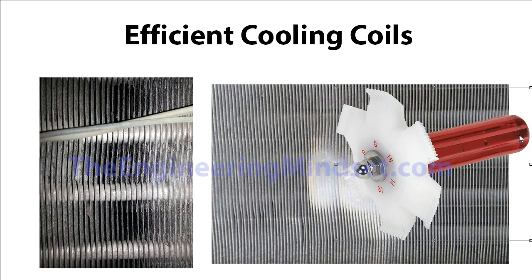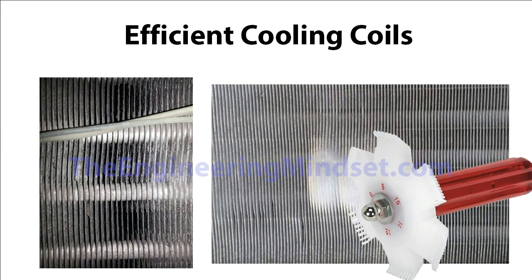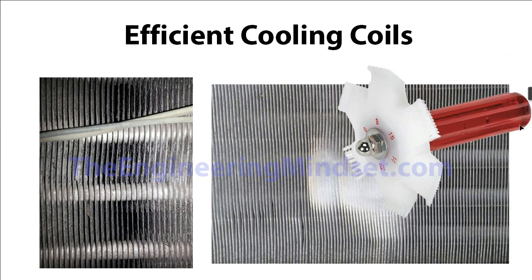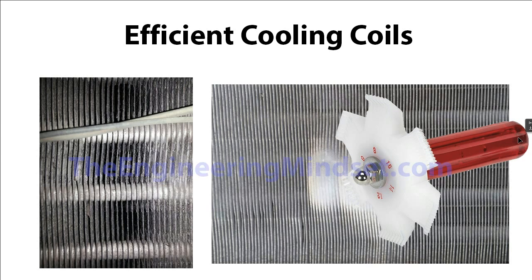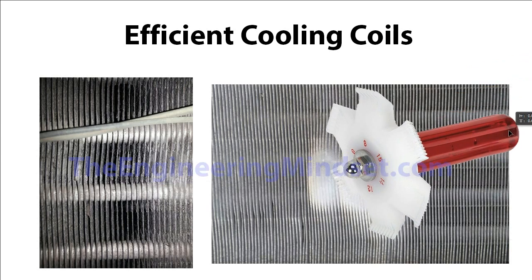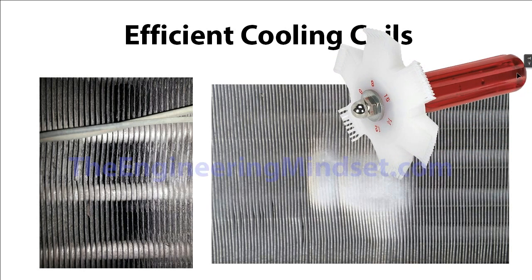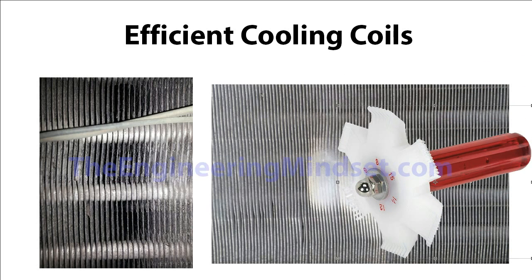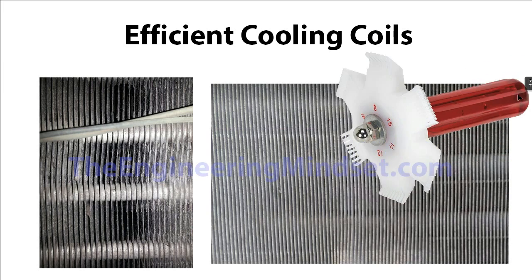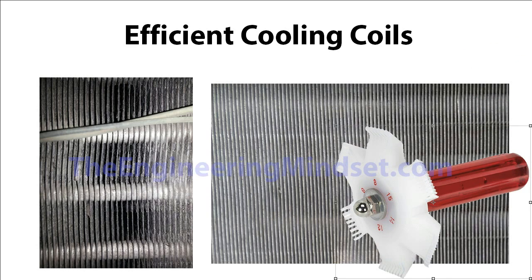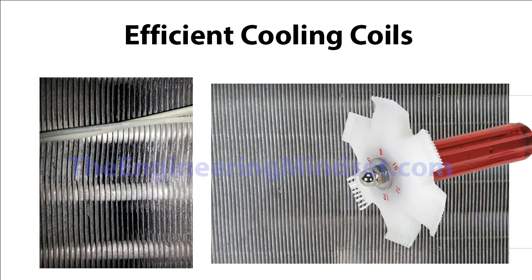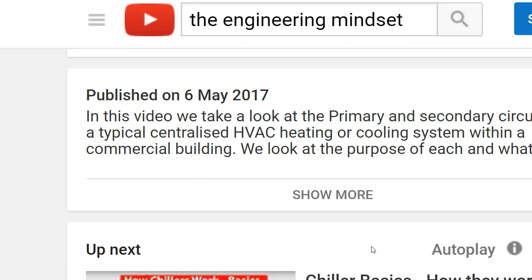You need to be very careful when working around these. If you do have some damaged fins, it's very easy to repair — you can buy a condenser fin comb, which looks a bit like this. They're very cheap, around ten pounds or ten dollars. You find the right size fin fitting and put it in like a comb, pushing it up and down a few times, and that will straighten out all the fins back to new. I've left some links in the description for where you can buy these — a very useful tool I highly recommend any HVAC engineer have.